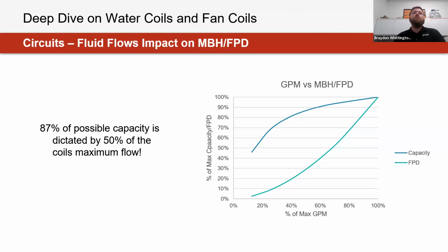So a common rule of thumb I see in industry, especially when dealing with circuitry with a coil, is that around the 2 GPM per circuit mark is where you're starting to get to maybe around 50% of the maximum GPM of that coil, which is a tempered mark of what you might set. That's going to get you around 80 to 90% of the capacity from that coil at a reasonable fluid pressure drop added to our system.